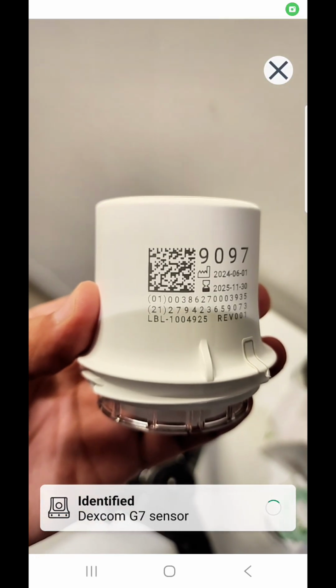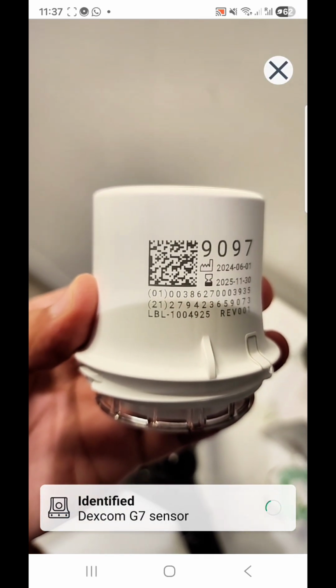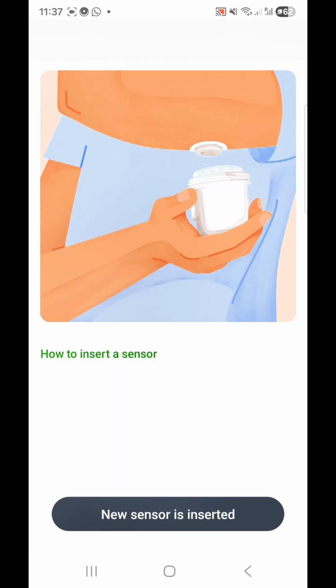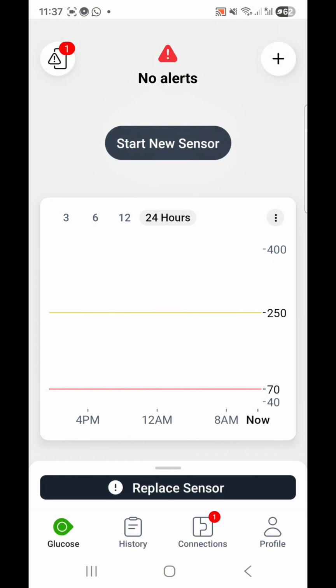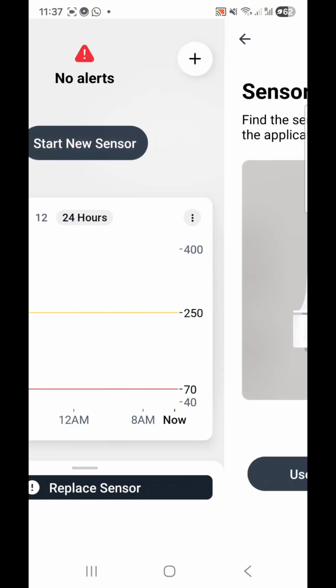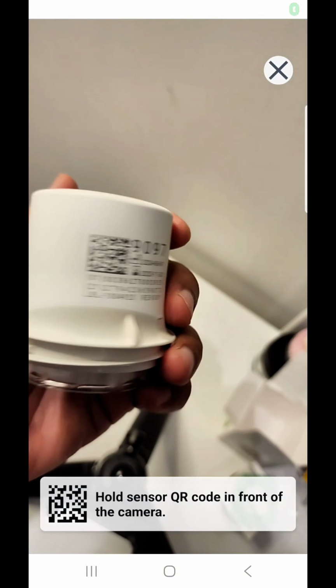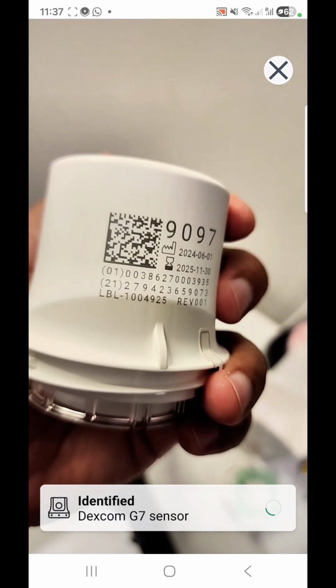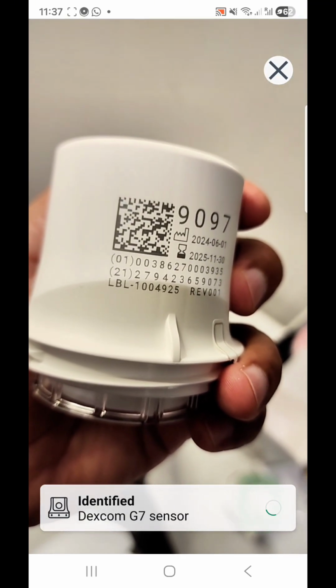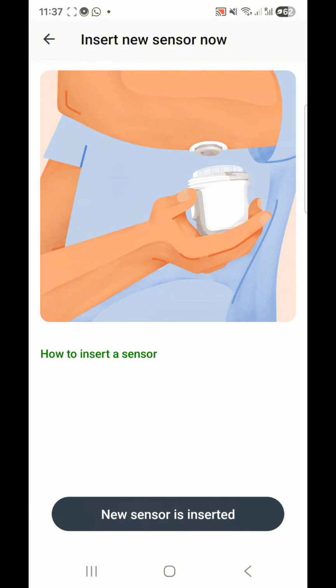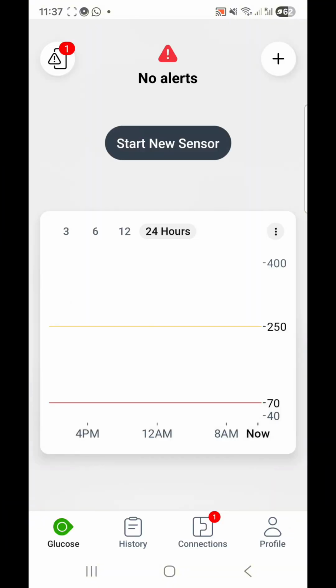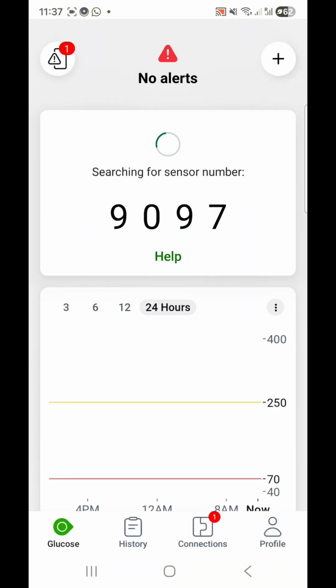So I'm going to use my camera to scan this QR code. I'm also aware that I've got the 9097 code to activate the sensor. You see the camera didn't work once, so I will try it one more time and try to scan it through the camera. If it doesn't work, then I will simply use this number manually to see if my Dexcom device can be scanned. And here you go, the new sensor has already been inserted and the code has been picked up. So my sensor is now ready.